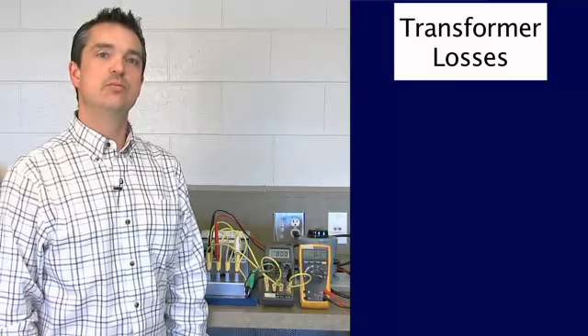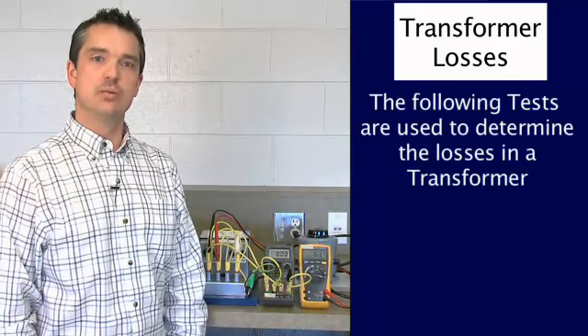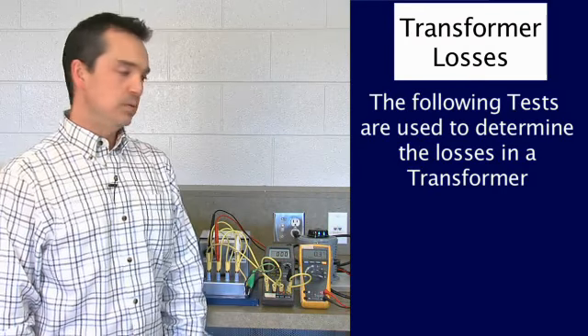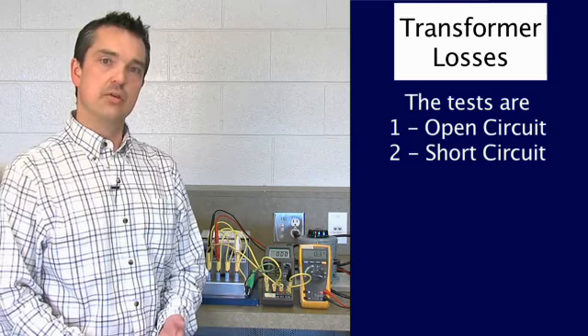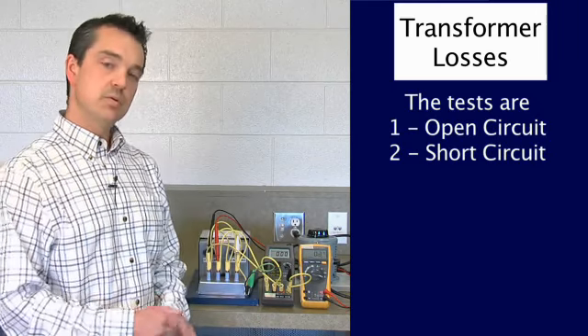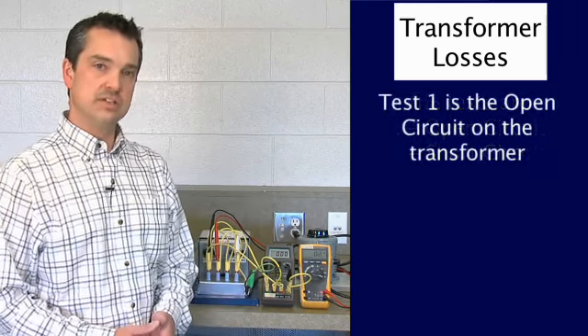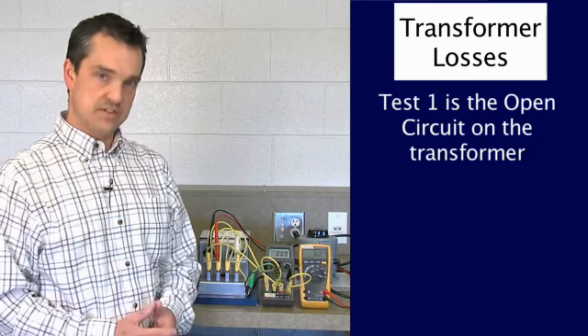Hi, we're here to perform a couple of tests on a transformer to determine the losses in a transformer. We have two different types of tests that we're going to do. One is an open circuit test, the other is a short circuit test. So the first one that I'm going to perform is an open circuit test on the transformer. I'll step you through the process of that.